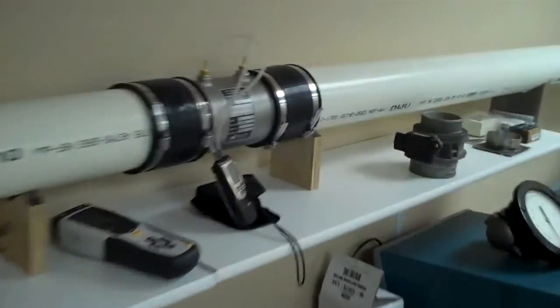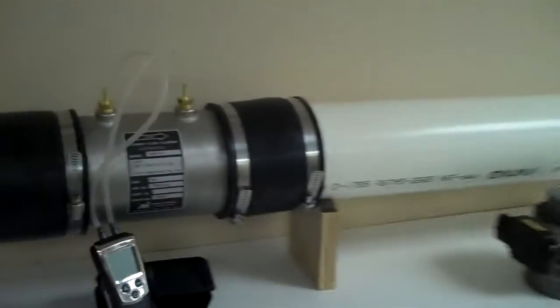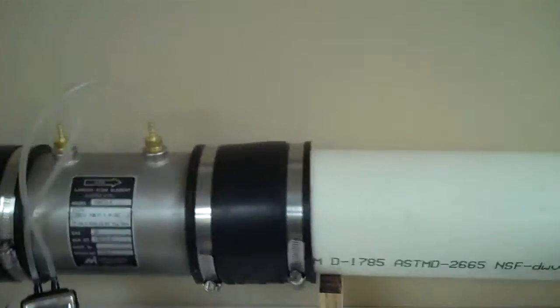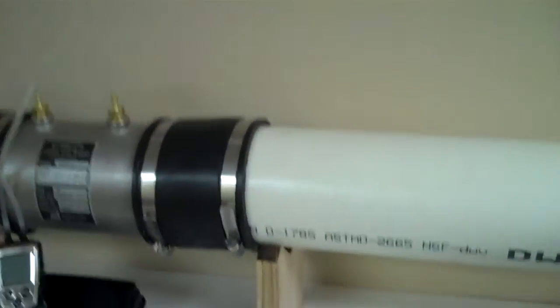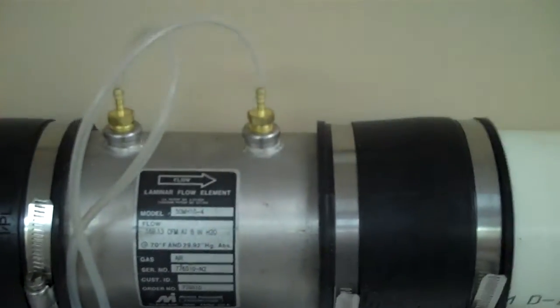Comes along here. Nice 90-degree elbow, and you will notice there's quite a long distance between before and after the laminar flow element because this needs basically direct flow of air as far as possible.